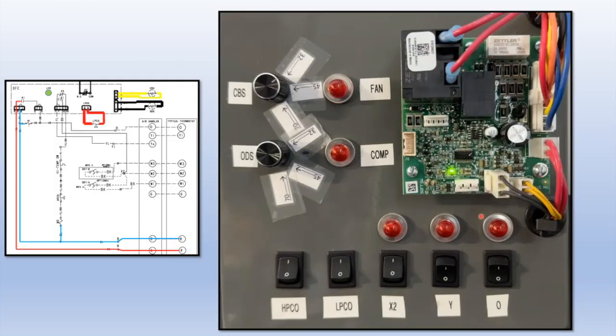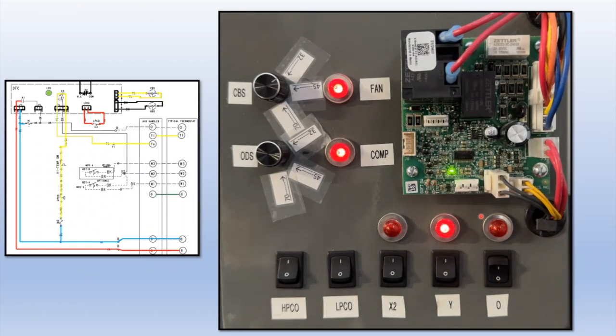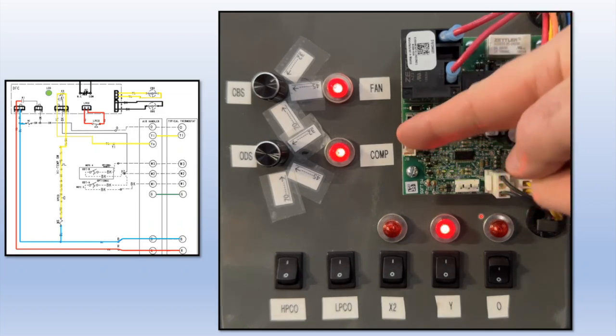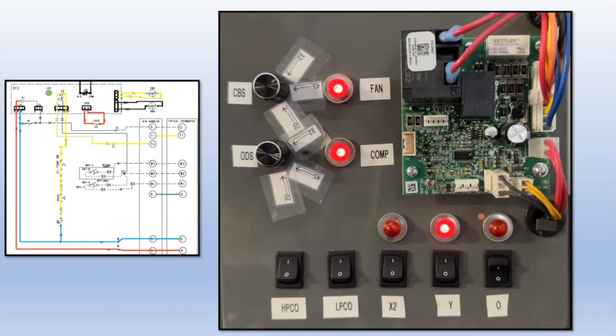We're going to go through the sequence of operation. First, we're going to give it a Y signal, which immediately turns on the compressor and the outdoor fan. So now we're in the heating mode of operation. The outdoor coil is getting cooler so that it can absorb heat energy from the outside air. At the same time, it might be building frost. So we're going to put it into a defrost mode by jumping these two forced defrost pins.